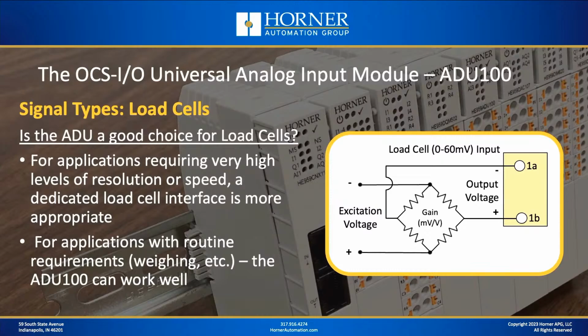Now, is the ADU a good choice for load cells? With the ADU, you have effectively a 0 to 60 millivolt input range, which is the only millivolt range that's supported. So is that appropriate for a load cell application? Well, the answer is it depends. If you have an application that requires very high update rates and very high resolution levels, then you're going to be better off with a dedicated load cell interface, a dedicated piece of equipment that's going to interface with your load cell and is going to come up with the reading that you can then pass on via another signal type or an industrial network or something back to the OCS.